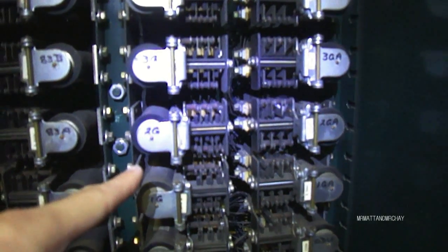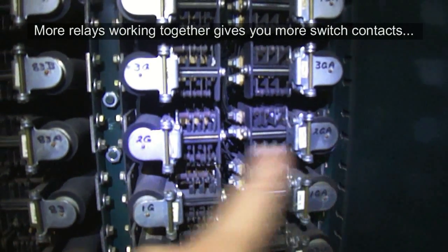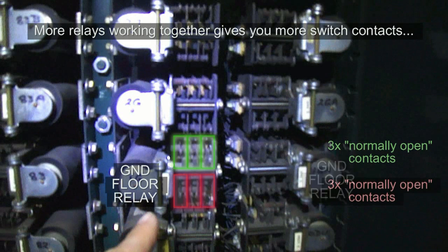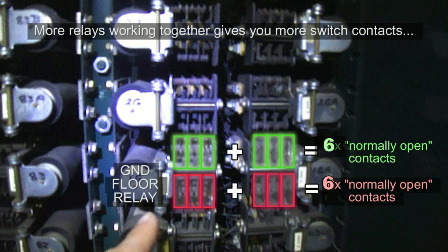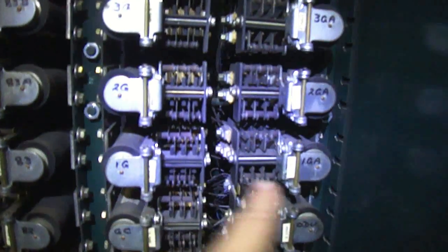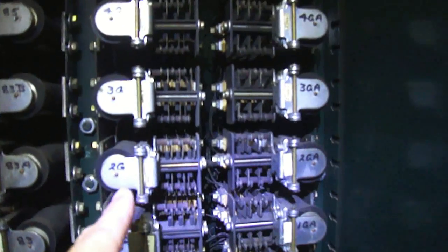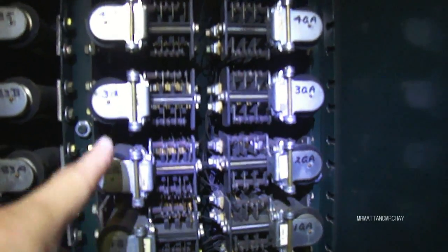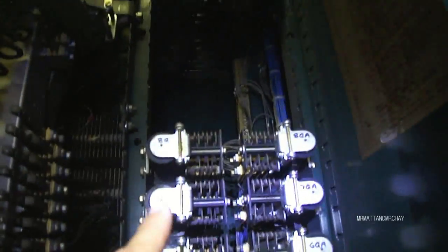So this is where the lift is, and these relays work together. These relays both come on if the lift's on the ground floor. These both come on if it's on the first floor, and all the way up to the seventh floor. So let's give it a go. It's on floor one at the moment, and floor one is that one there. There's a ground, there's one.